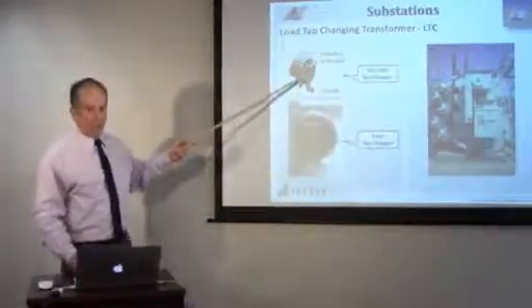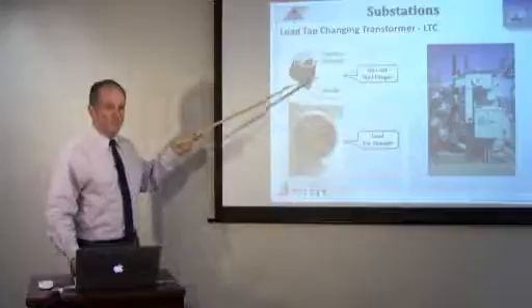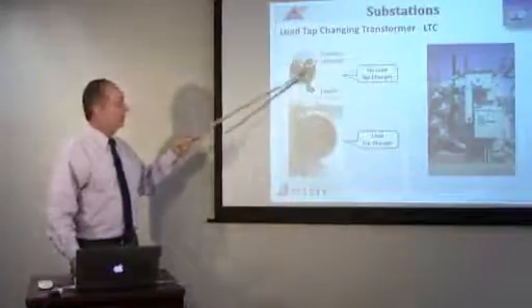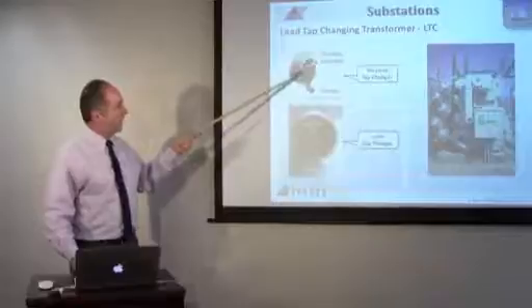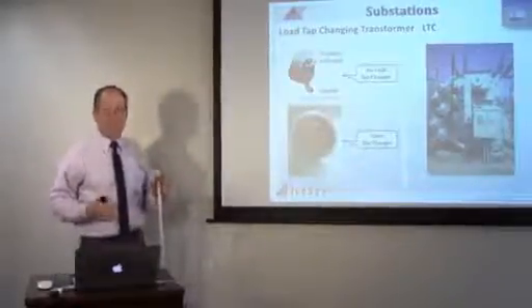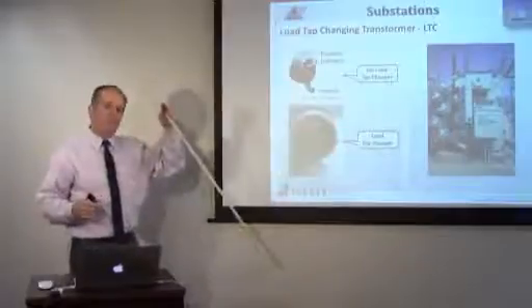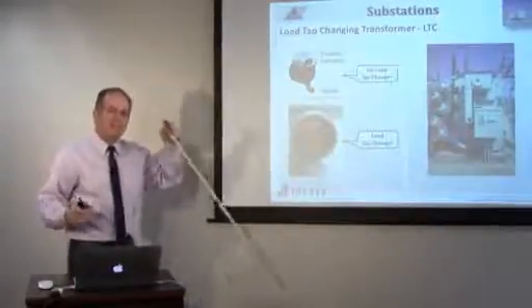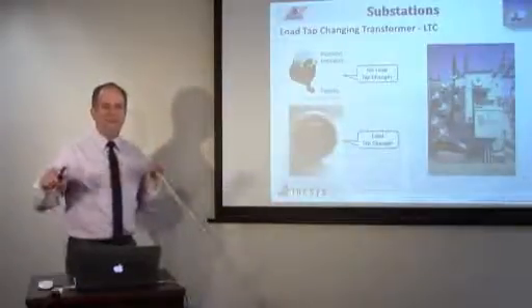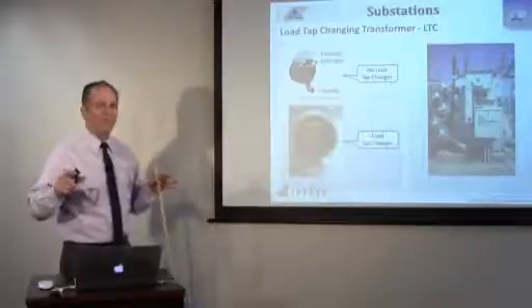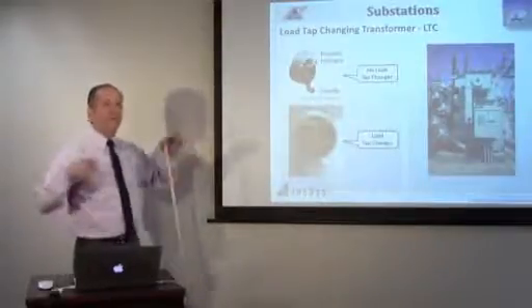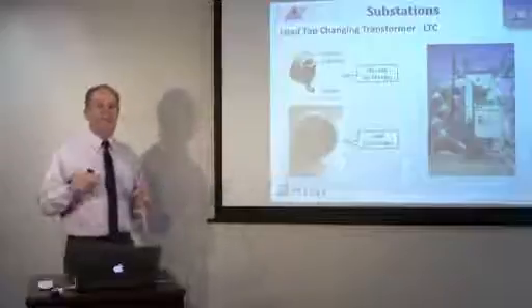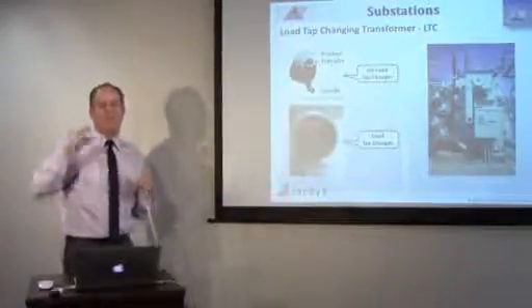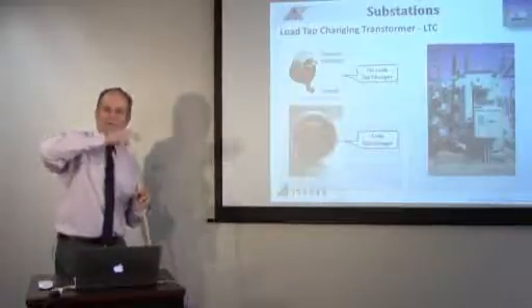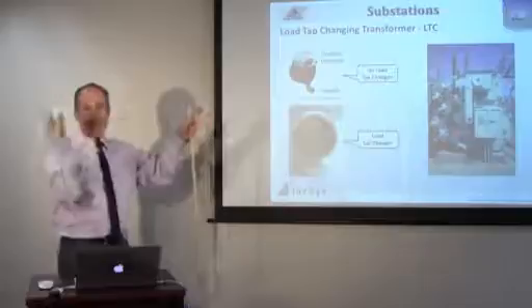This is a no load tap changer. It means no load. De-energize a transformer if you're going to change one of these taps. And these are usually taps on the primary, the high voltage winding. It's like saying if I have a 20-to-1 turns ratio, this might be 21-to-1 or 22-to-1. Give you a little variation in the actual turns ratio. So if your system voltages need to be changed or matched or whatever, you de-energize a transformer, change this, and then re-energize and connect everything back up, and it kind of gives you a little step up in voltage. It helps center the regulator, so maybe the regulator is way off on one end all the time. Changing the main tap, now it might be centered better. Those are no load tap changers.